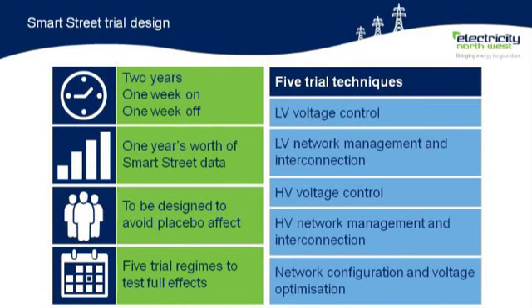The trial design is based around a 1 week on, 1 week off test scenario, and will run for a full 2 years. Essentially the 1 week off test scenario will provide a year's worth of baseline data, and for this baseline data we will be running the networks in the historic configurations, i.e. radial configurations in historic tap positions with no automation.